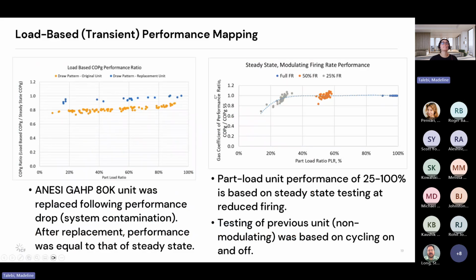And looking at the load-based testing, in the event of looking at the draw pattern, there were some issues with the unit itself. There was some contamination of the refrigerant. You can see the difference we have outlined here with the draw pattern on the original unit. That was the original unit that we found had some contamination. It happened in the expansion valve of the system. We tried flushing it out, but that didn't correct the issue that was being seen. So a full replacement unit was set, and you can see the difference in the performance, where it was performing back up to the expected conditions.